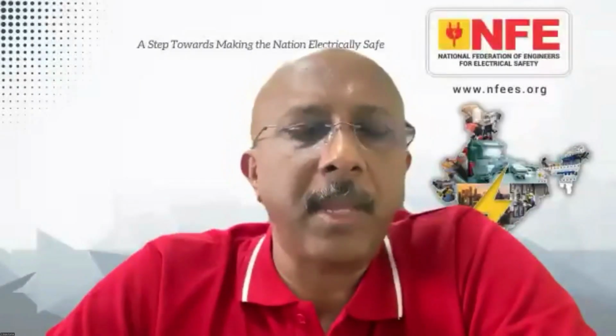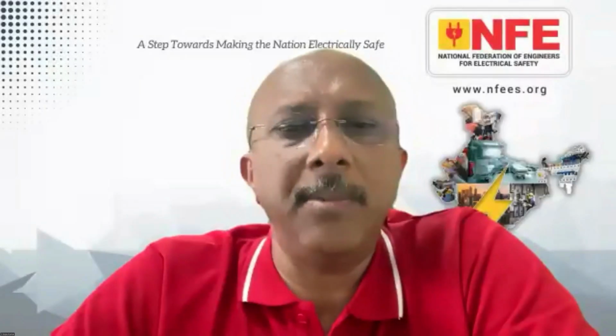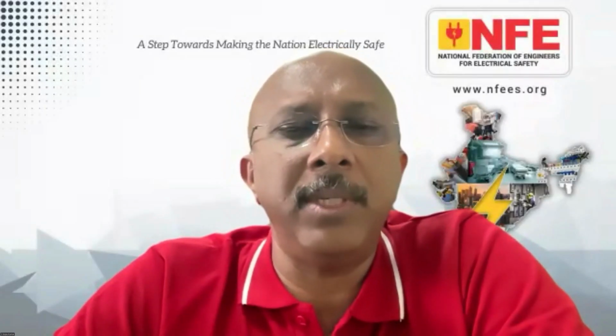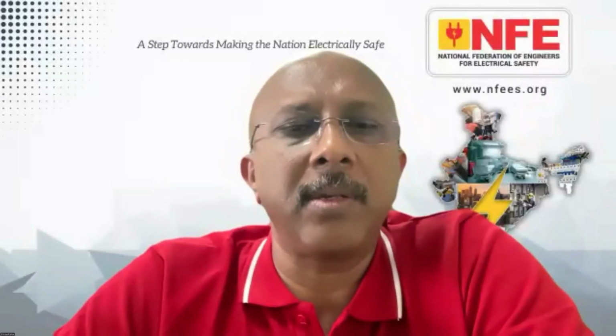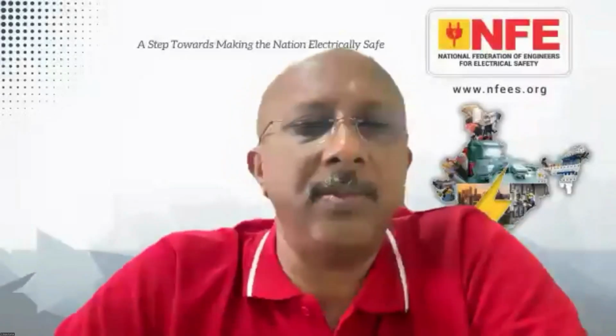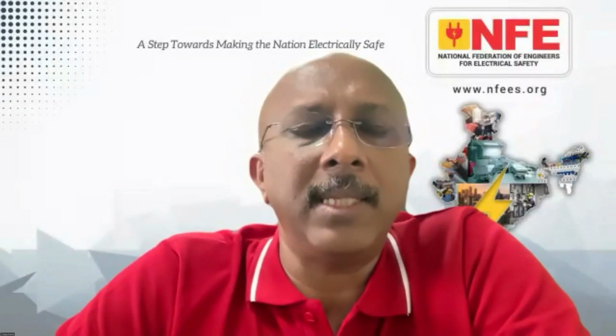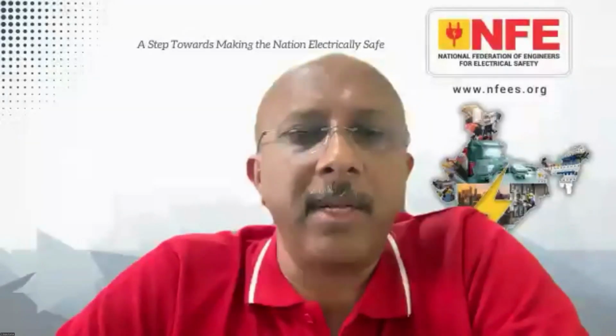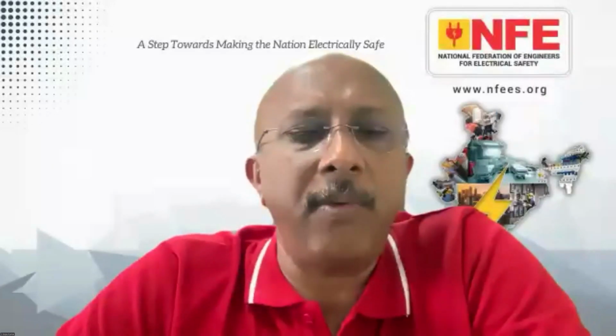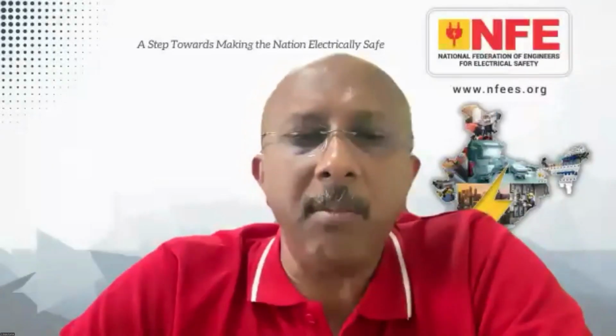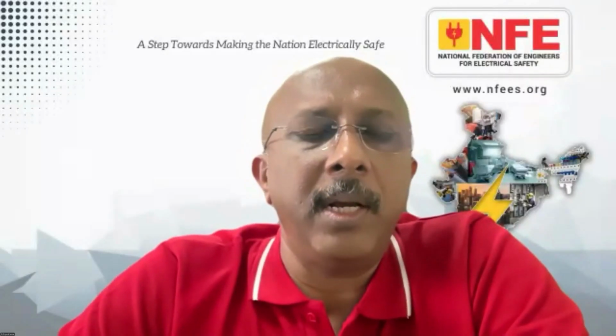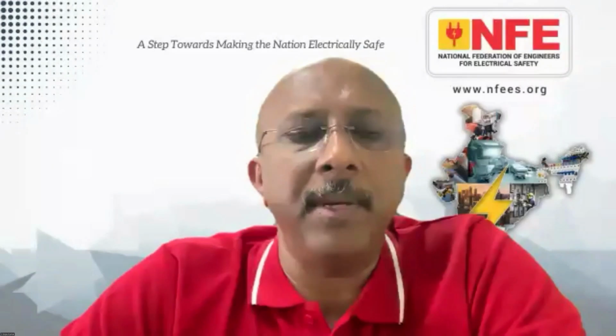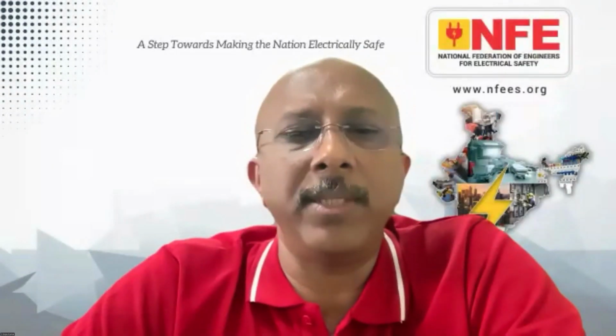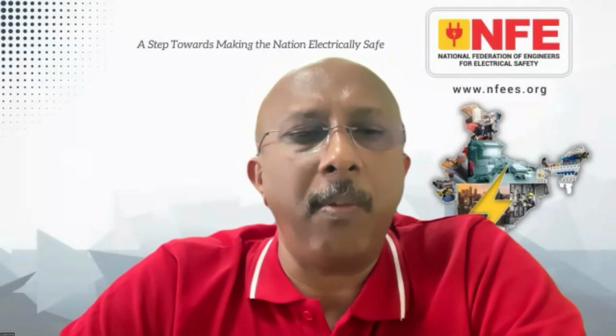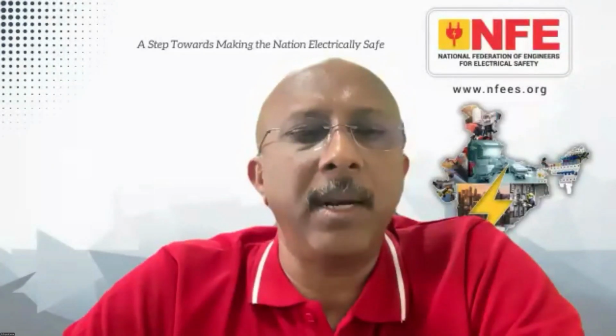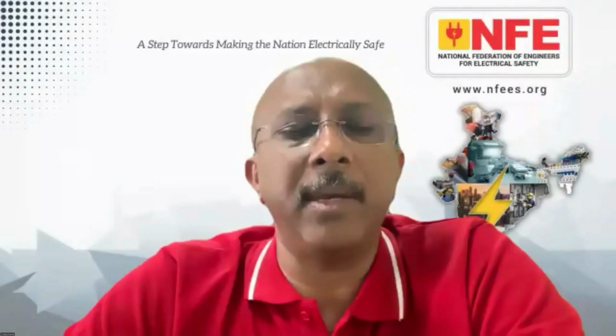Number two, as per the rules and regulations, the distribution company is supposed to give you electricity within a certain tolerance. Such drastic fluctuations, where we need to use a stabilizer, have to be avoided by the DISCOM. But unfortunately, we all know the situation of our DISCOMs very well. More than that, there is a third problem. Faults in the HT system are creating a lot of failures in low voltage consumer premises. These problems are already explained in IS 732, especially in clause 4.5, but who will implement it is the question.